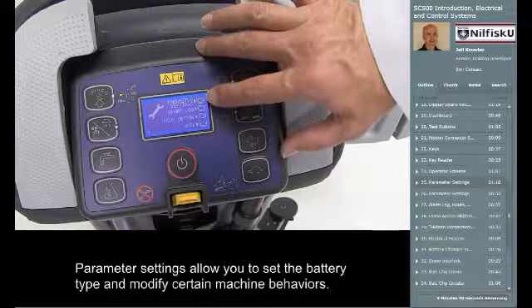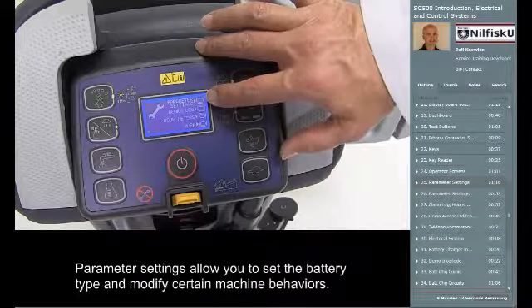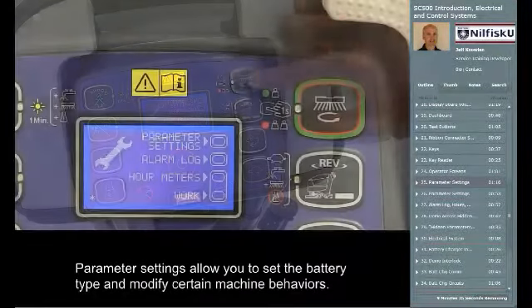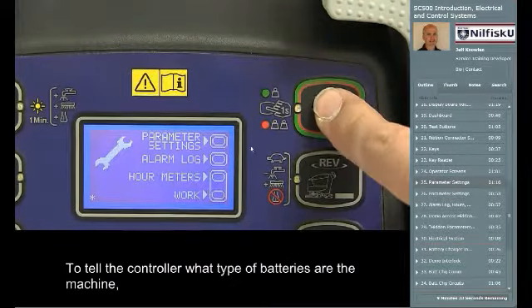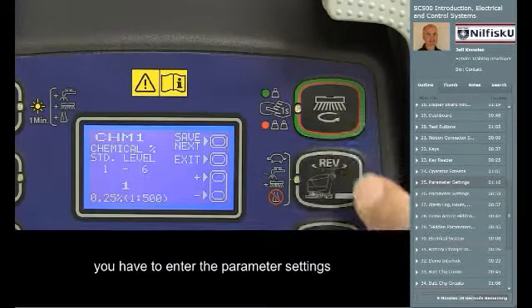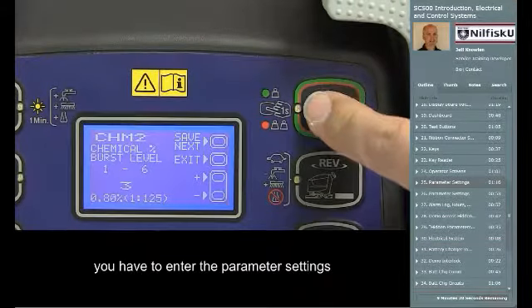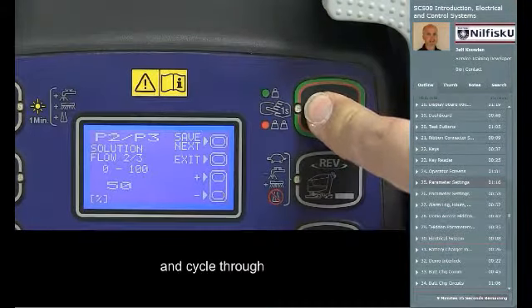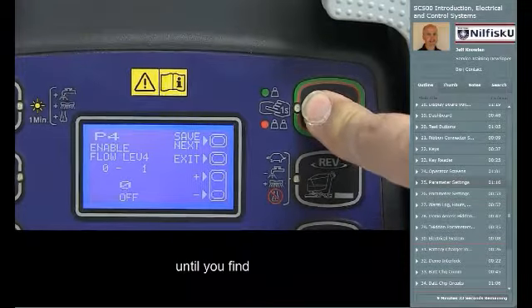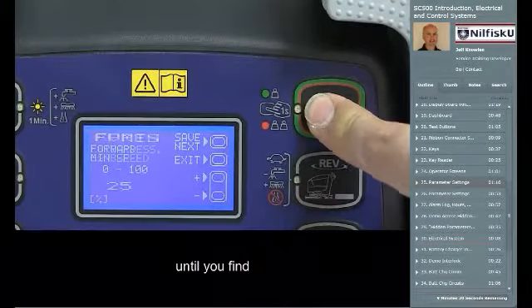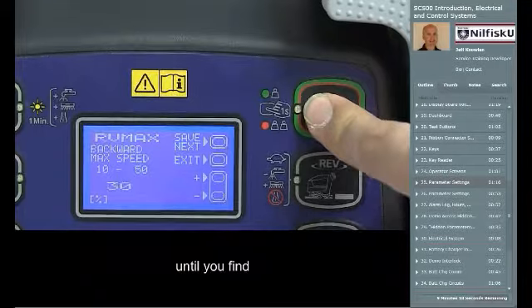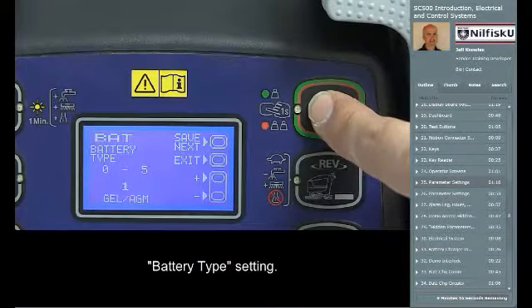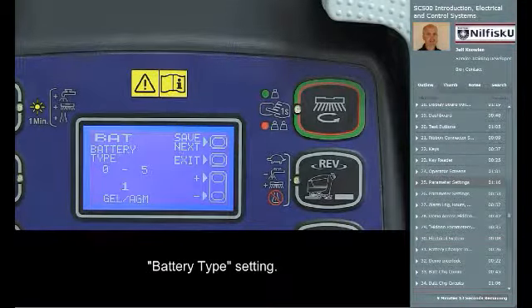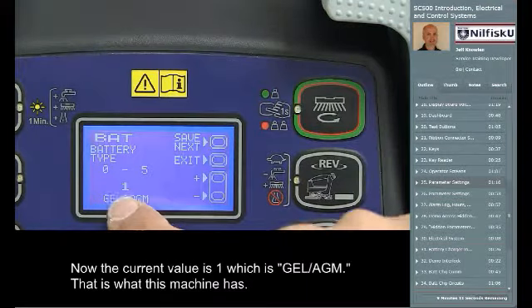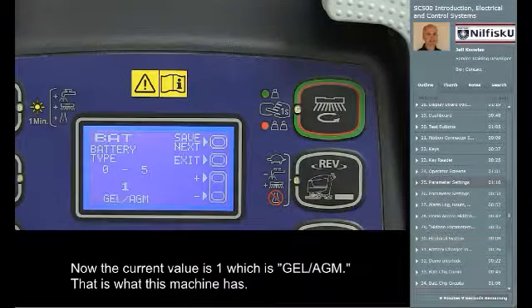Parameter settings allow you to set the battery type and modify certain machine behaviors. To tell the controller what type of batteries are in the machine, you have to enter the parameter settings and cycle through until you find the battery type setting. Now the current value is 1, which is a gel or AGM. That is what this machine has.